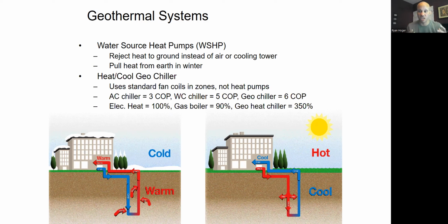But if your ground is stationary, it's like a storage battery. You're just heating up that granite, or whatever ground you have, heating it, heating it. And it takes so long for heat to move from rock to rock to rock underground that it would take years to dissipate all that heat. So you are degrading the temperature of the ground when you don't have a balanced load on a looped geothermal system where the ground is pretty hard material.